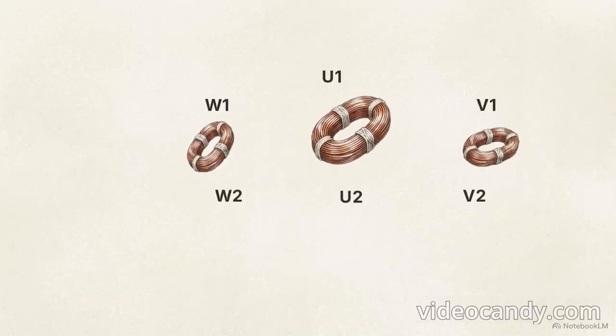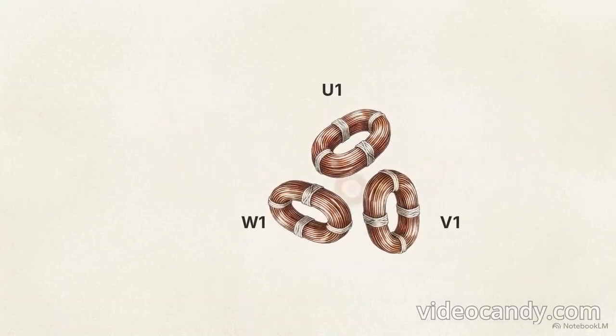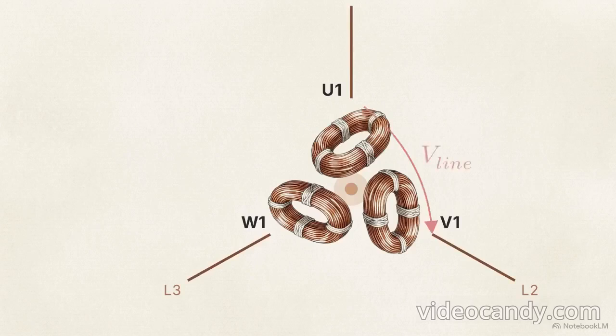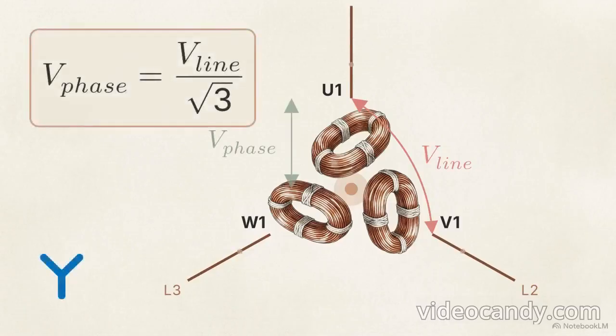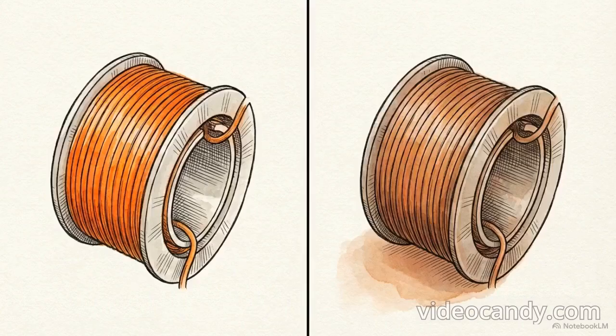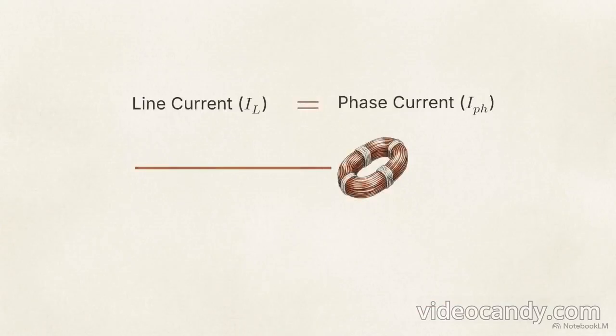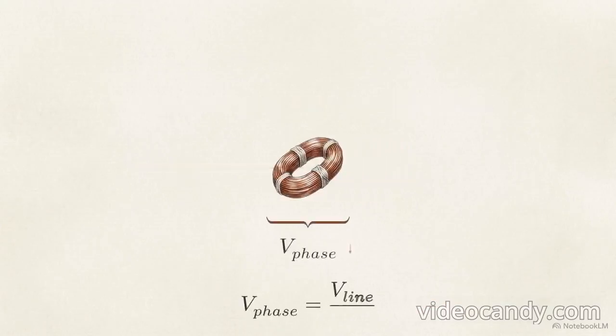The starting process relies entirely on the first of 2 distinct electrical states, the star or Y configuration. To form this geometry, the physical connection involves shorting the 3 back ends of the coils, U2, V2, and W2, together. This creates a common neutral point, while the 3 incoming grid power lines attach to the outer tips. The physical layout changes the math of the circuit. In this geometry, grid supply line voltage is no longer applied directly across any single motor coil. Instead, voltage dropped across any individual phase winding equals total line voltage divided by the square root of 3. Mathematically, this dictates that only 58% of the full line voltage reaches the motor's windings.